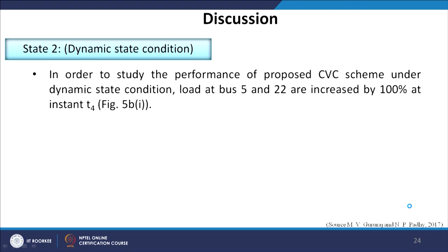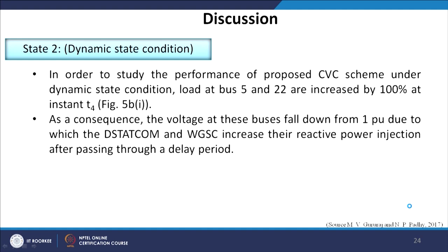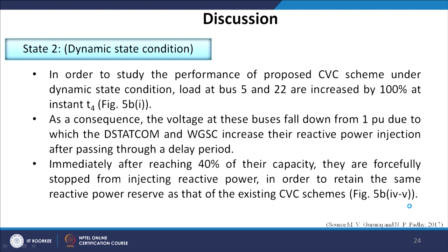For state 2 (dynamic state), to study the proposed CVC scheme performance, the load at bus numbers 5 and 22 is increased by 100 percent at instant T4. As a consequence, the voltage at these buses falls from 1 per unit, causing the DSTATCOM and WGSC to increase reactive power injection after passing through a delay period. Immediately after reaching 40 percent of their capacity, they are forcefully stopped from injecting further reactive power in order to retain the same reactive power reserve — consistent with the existing CVC scheme.